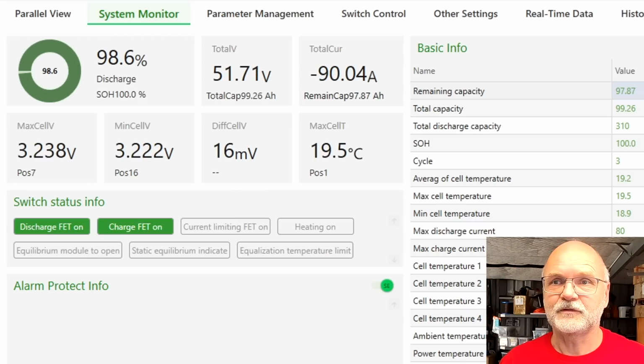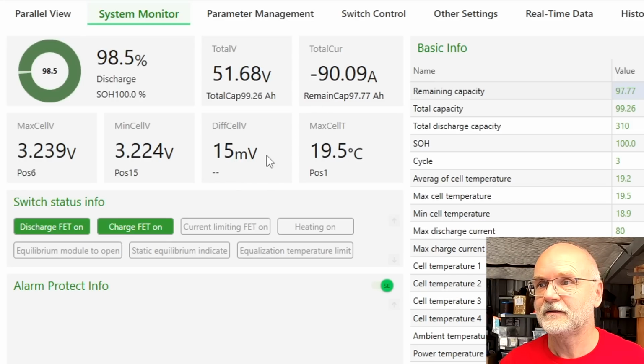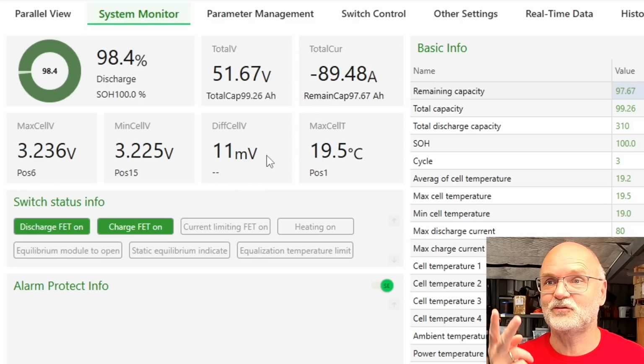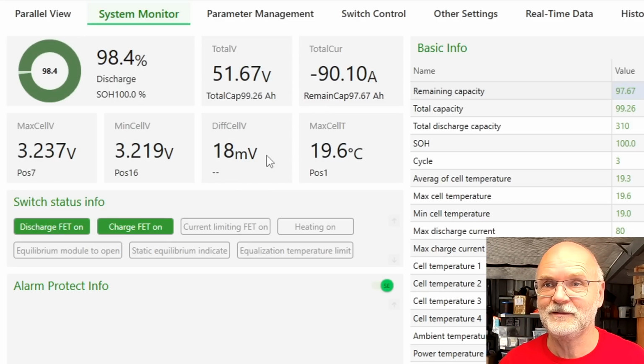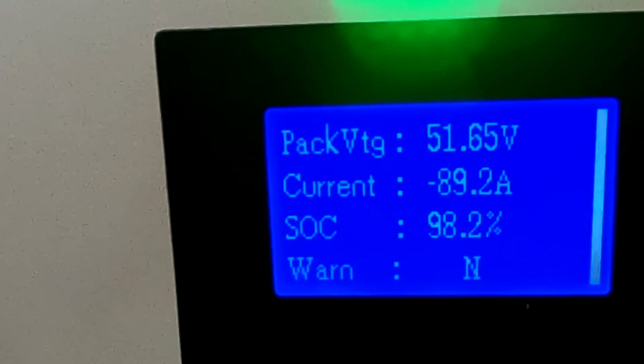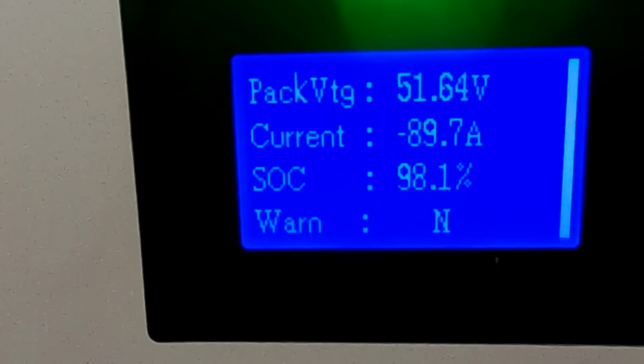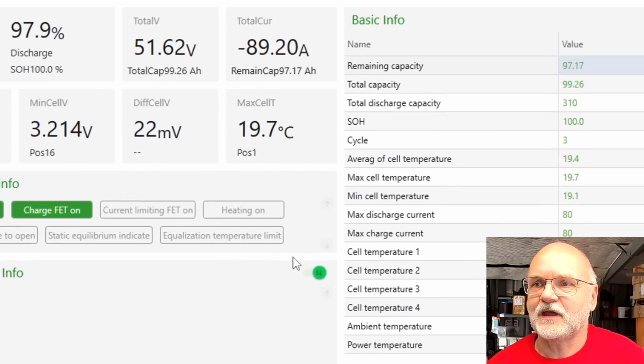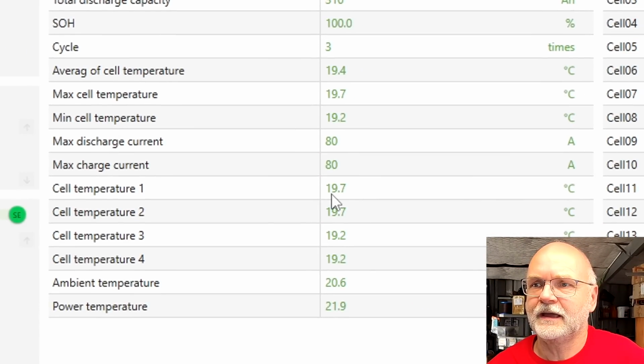So 16 millivolt deviation we have. We're pulling 90 amps now. 8 millivolt. I've got two inverters connected to the Seplos Polo battery. Oh yeah, we are pulling 90 amps here. Wow. That is insane. Also, let's have a look at the temperature sensors. They are all on 19.7, 19.2, ambient 20.6. So that all looks good.